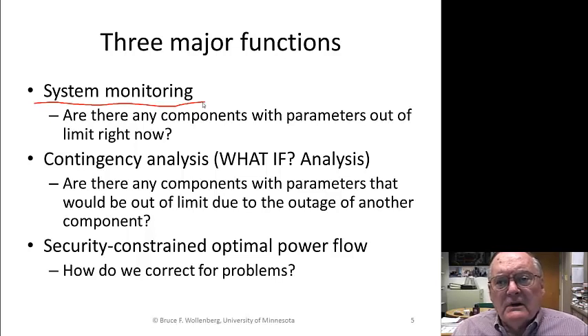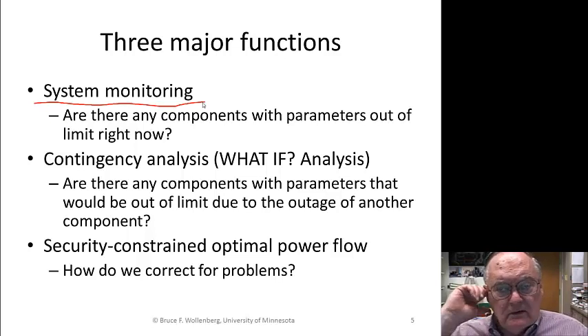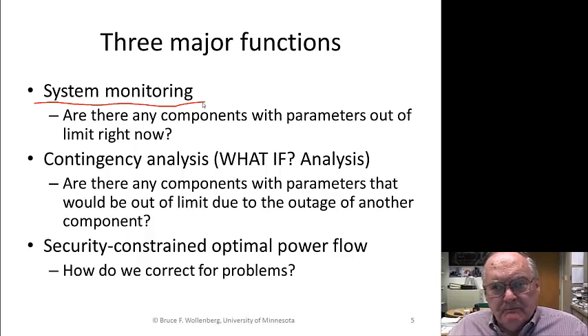Anything that comes out where it says it's either too much flow, too much current, or too low a voltage, we put an alarm, and the alarm is literally, well, there's an example of an alarm, okay? My cell phone giving me a small alarm. And the value of the alarm is that it rings a bell, like you heard there, and that alarm gets the operator's attention, and the operator has to do something.